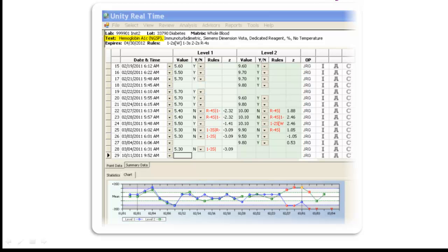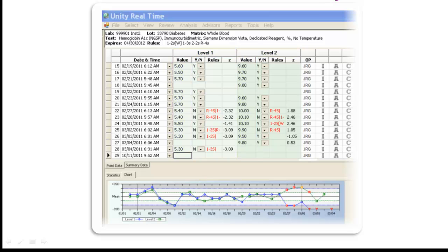The laboratory needs to document that quality control materials are assayed and that the quality control results have been inspected to assure the quality of the analytical run. This documentation is accomplished by maintaining a QC log and using the Levy-Jennings chart on a regular basis. The QC log can be maintained on a computer or on paper. The log should identify the name of the test, the instruments, units, the date the test was performed, the initials of the person performing the test, and the results for each level of control assayed. Optional items include method and assay temperature, usually included for enzymes. There should be room to write in actions taken to resolve any out-of-control situation, and a place for documentation of supervisory review.